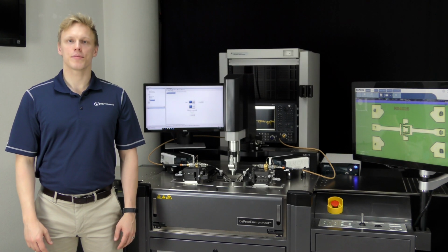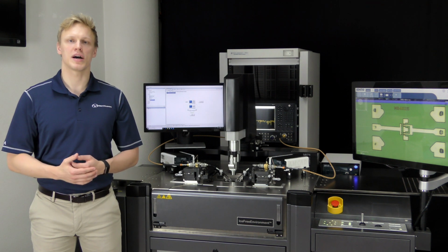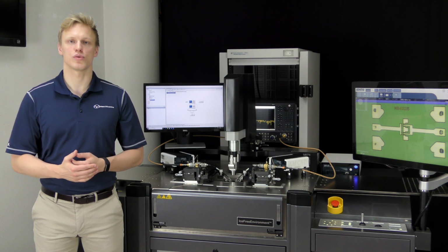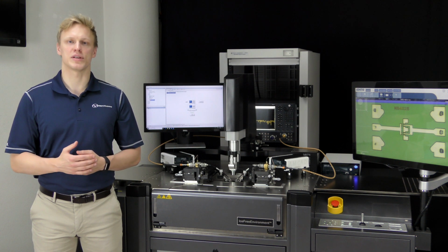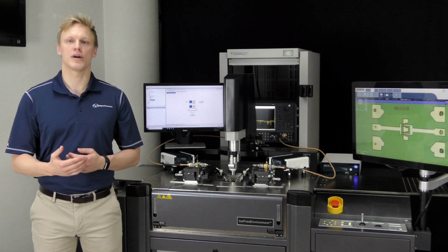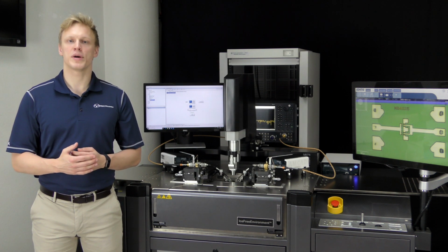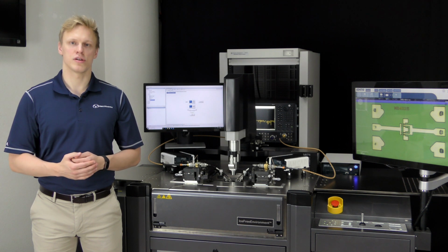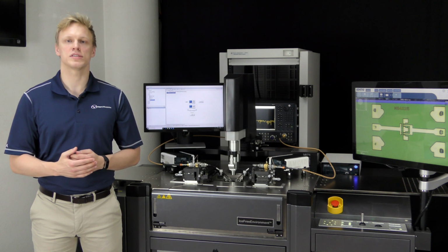With the AMCAD AM3200 series pulsed IV system, we can provide a pulse gate bias between -25 volts and 25 volts, currents up to 1.3 amps, and measure with a 16-bit resolution. We can provide a pulse drain bias between 0 and 250 volts, with currents up to 30 amps, and measure with an 18-bit resolution. All this with pulse widths as low as 200 nanoseconds and asynchronous long pulses up to 200 seconds.